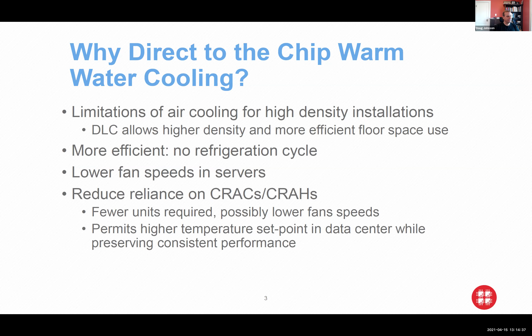And there were a couple of things that pushed us towards this. We're in a data center that was not purpose-built for high density or HPC, and we don't have any chilled water available in our space, and the chiller plant in the building is just not large enough for the scale of systems that we put in.